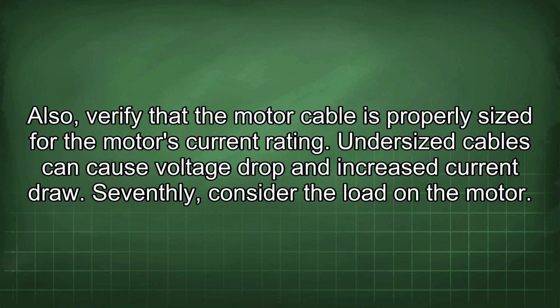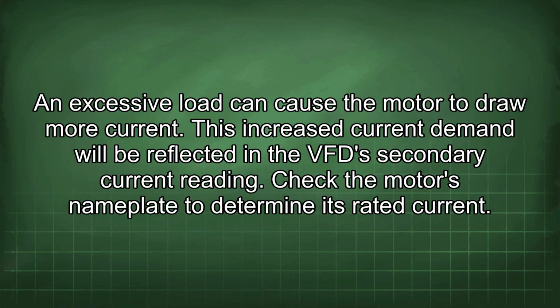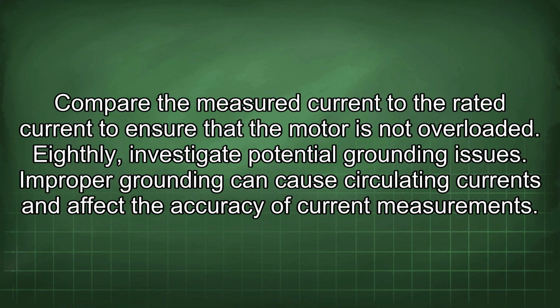Seventhly, consider the load on the motor. An excessive load can cause the motor to draw more current. This increased current demand will be reflected in the VFD secondary current reading. Check the motor's nameplate to determine its rated current. Compare the measured current to the rated current to ensure that the motor is not overloaded.